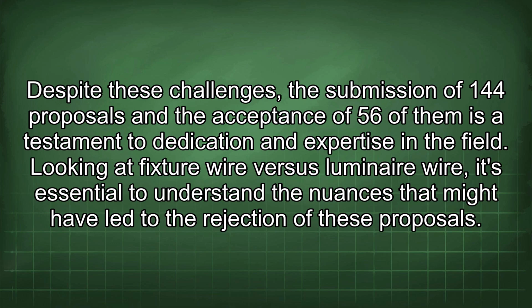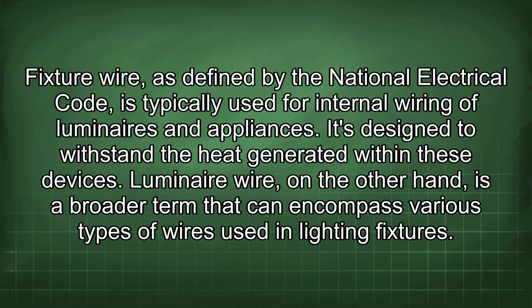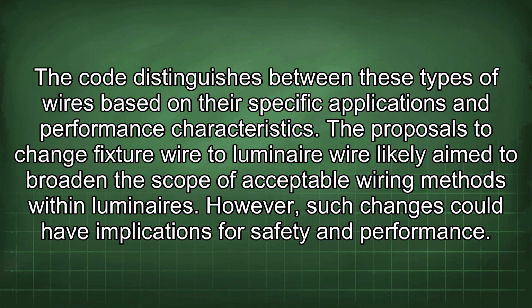Looking at fixture wire versus luminaire wire, it's essential to understand the nuances that might have led to the rejection of these proposals. Fixture wire, as defined by the National Electrical Code, is typically used for internal wiring of luminaires and appliances. It's designed to withstand the heat generated within these devices. Luminaire wire, on the other hand, is a broader term that can encompass various types of wires used in lighting fixtures. The code distinguishes between these types of wires based on their specific applications and performance characteristics.